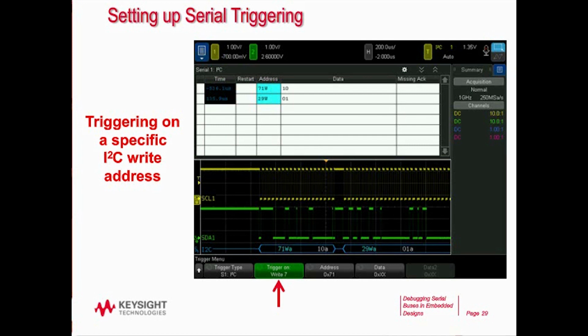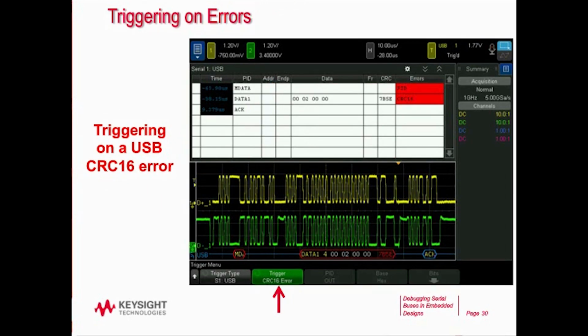You can also set the values to don't cares, or one byte with a specific value and a don't care on the other byte. If you want to know every time your USB design has a CRC error, use the CRC16 trigger. This will show you one CRC error. But what if you want to know every time and how often this error is occurring?